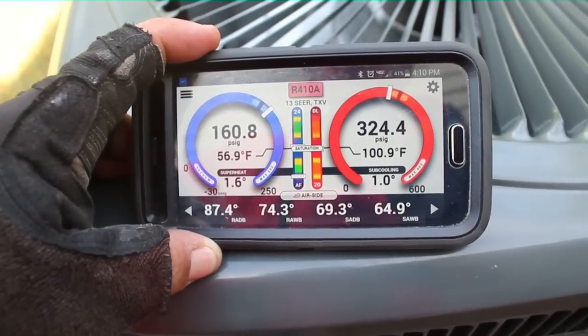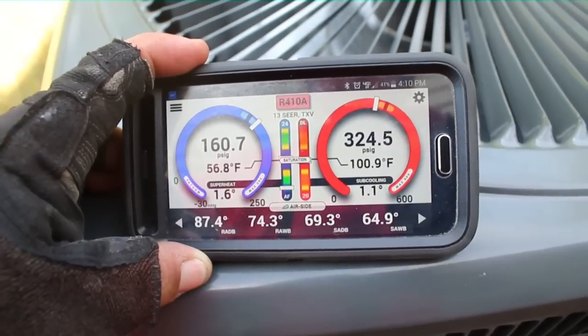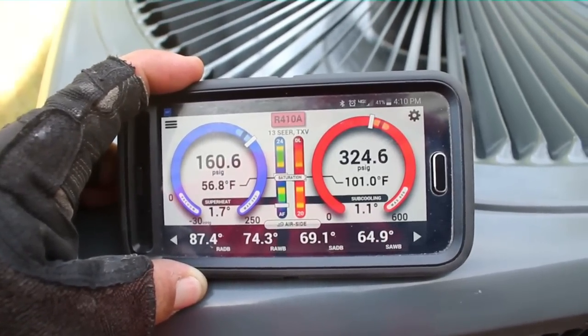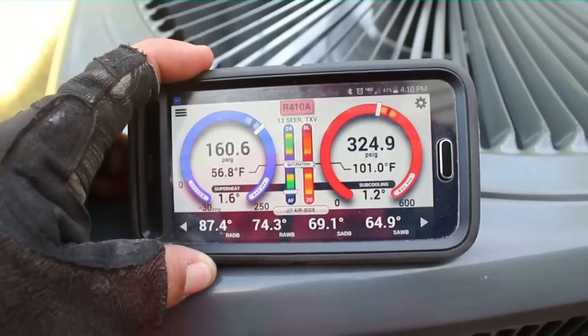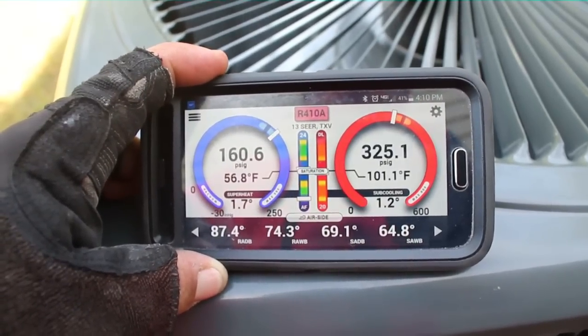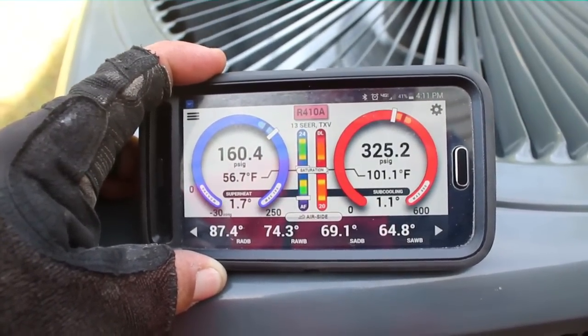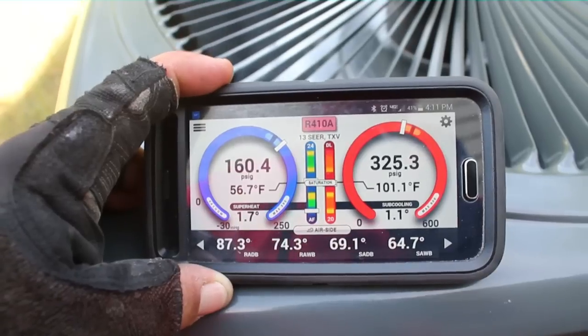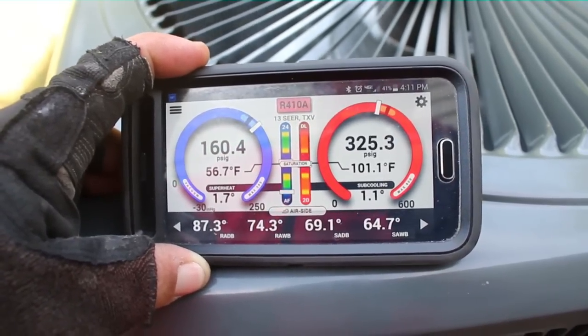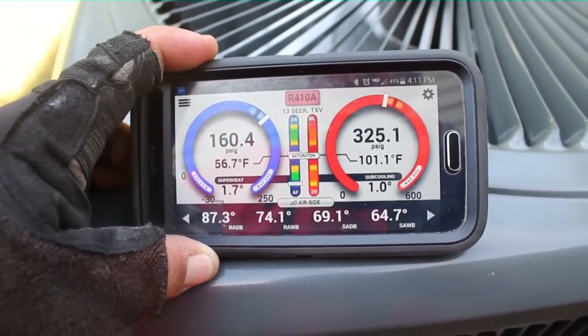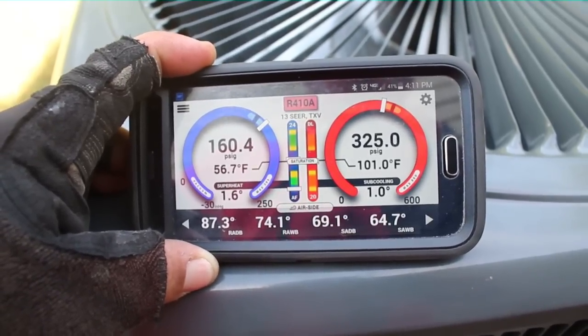That will increase the superheat and subcooling, basically throttling back the TXV so more of the refrigerant stays on the condenser side, raising the subcooling, and less of it makes it to the evaporator, which will raise the superheat. But right now they might adjust out. We're going to give it a few minutes and either wrench it back, which will probably be the case, and let's see if we have to add any more refrigerant.